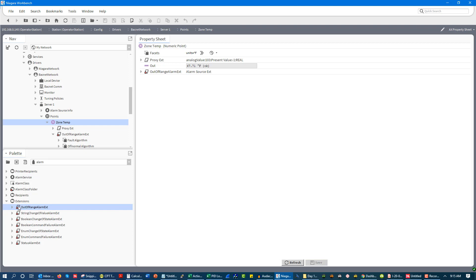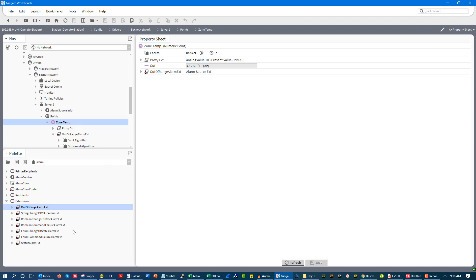Now there's typically three types of alarms. You have numeric alarms or basically number value alarms, analog alarms. You have Boolean alarms. These are basically true, false status alarms. And then you have enumerated alarms, which are based on states. So if you're doing any sort of state logic, maybe you're looking at multiple conditions and then determining that based on these conditions, you're in a specific state. And if you go in that state, you're going to have an alarm. So those are where you can use enumerated alarms.